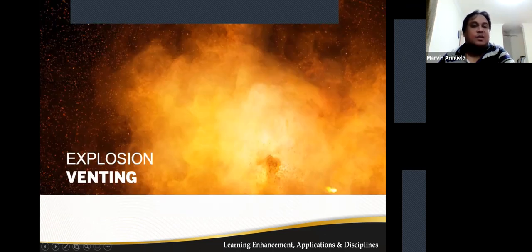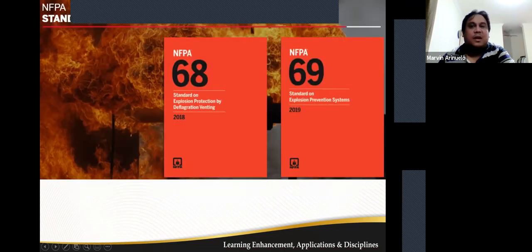Let us discuss now the explosion venting. The explosion venting is according to NFPA 68 and 69. The two standards address, again, the protection for explosion and deflagration. NFPA 68 is the standard on explosion protection by deflagration venting, and NFPA 69 refers to the standard on explosion prevention systems.